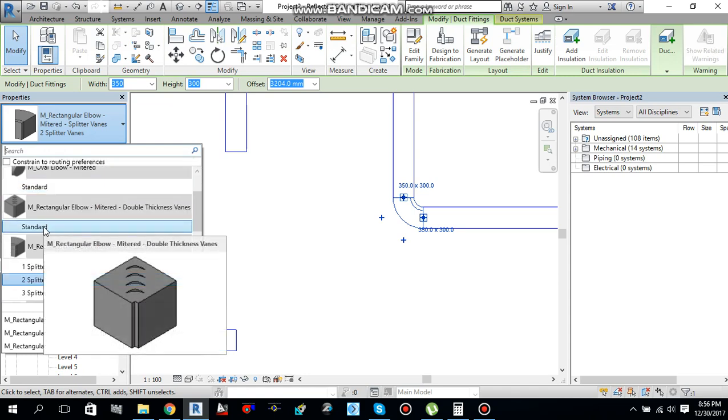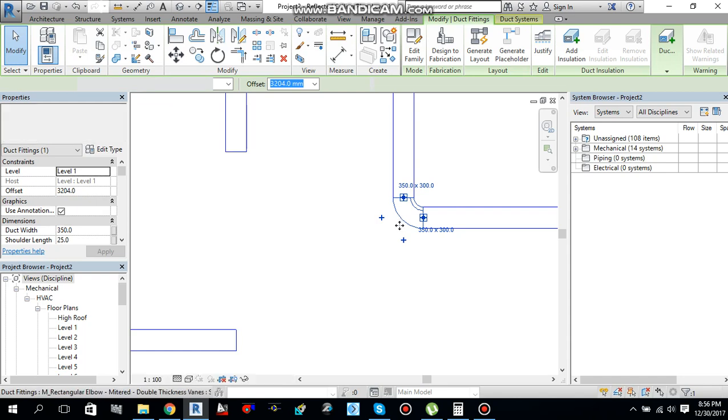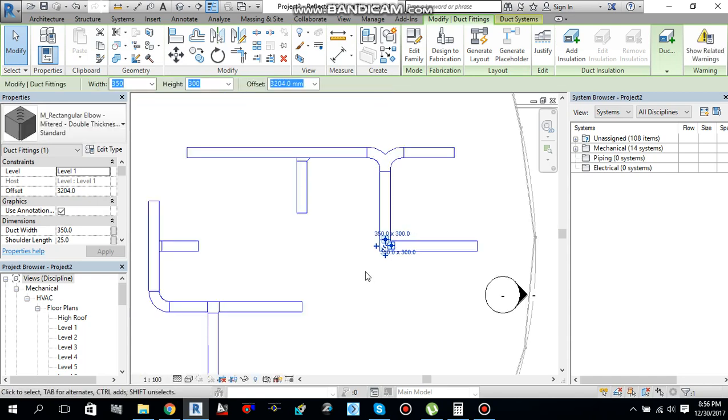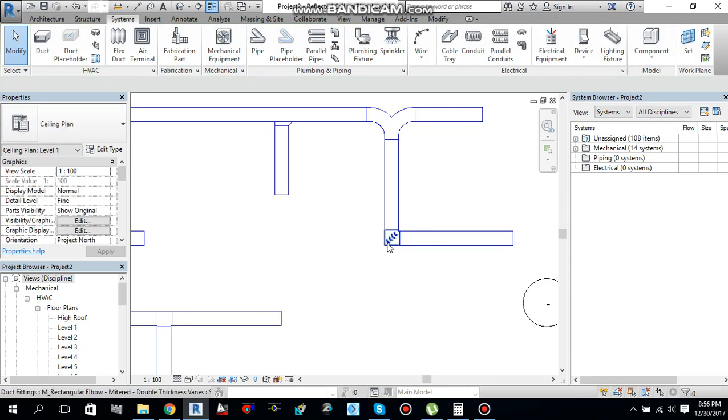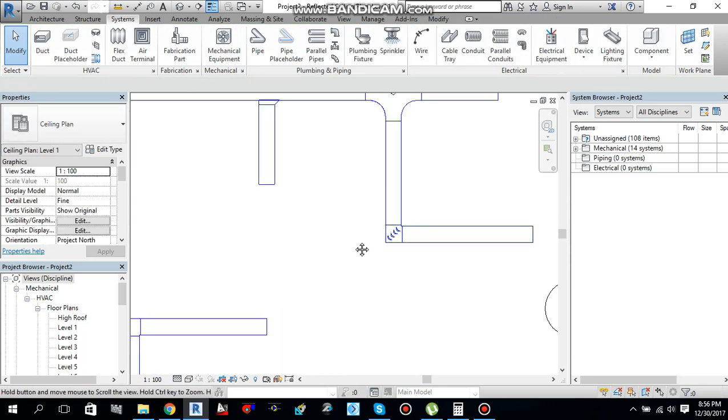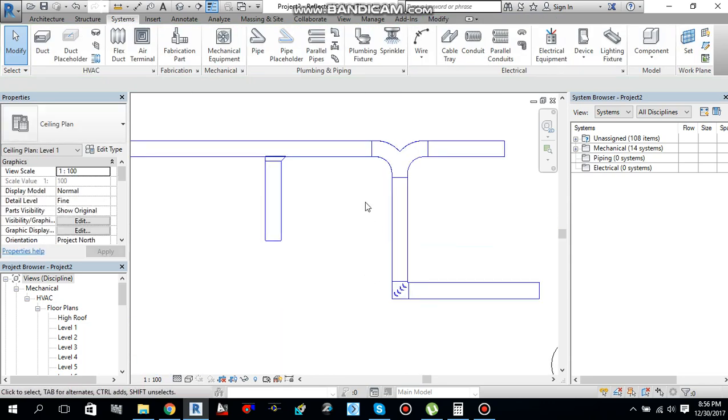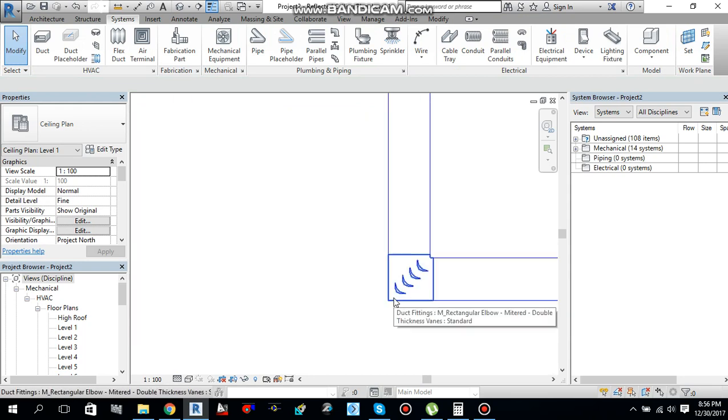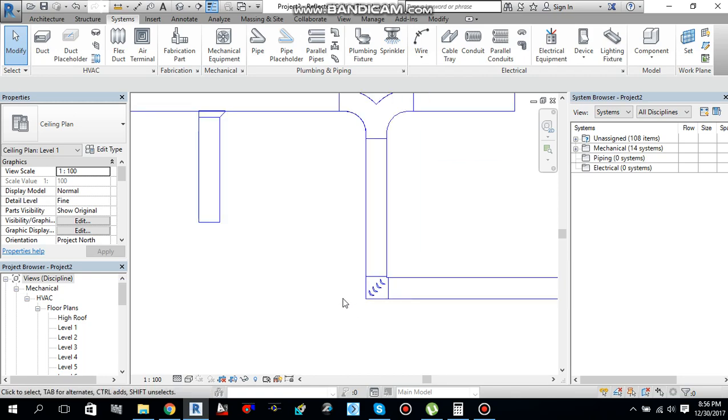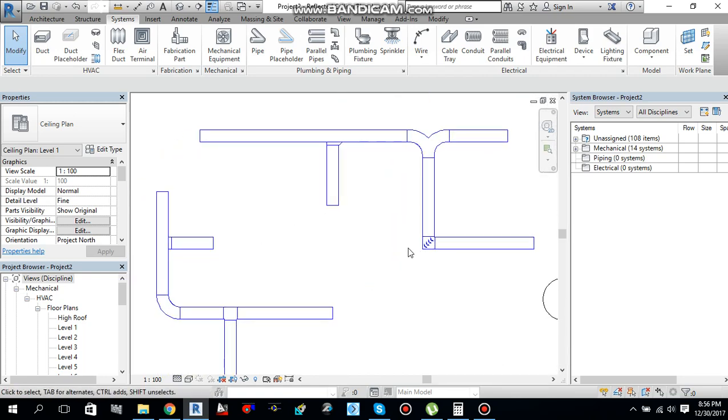For example, if I want to change this one to rectangular elbow, mitered double thickness vanes, I can select this one, and this elbow will be changed to rectangular, mitered double thickness elbow. So, sometimes you have space restriction. So, this is very important thing for you to know. You can change this elbow from a long radius to a short radius or rectangular to some other elbows.